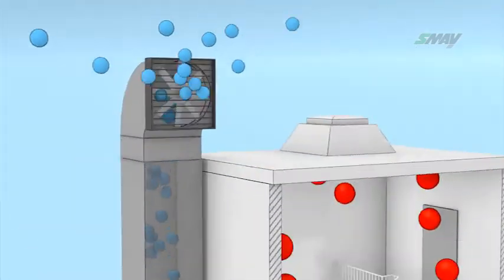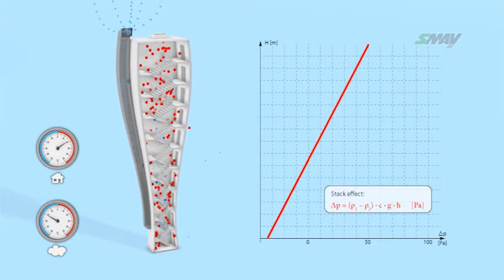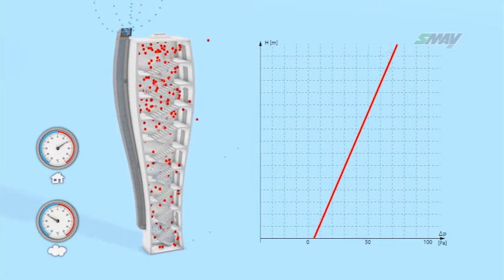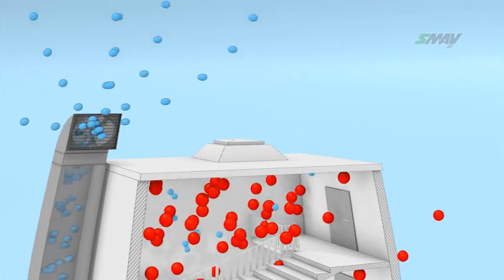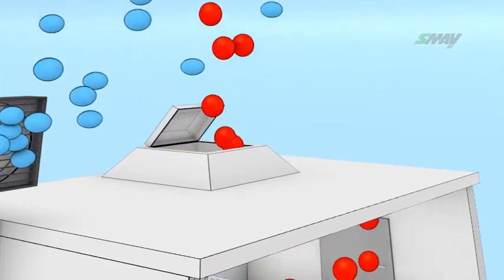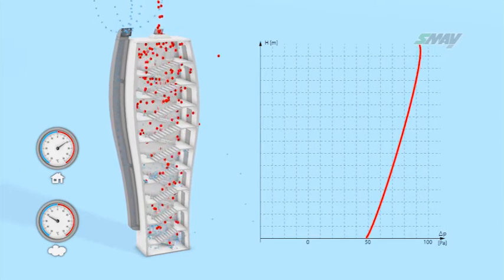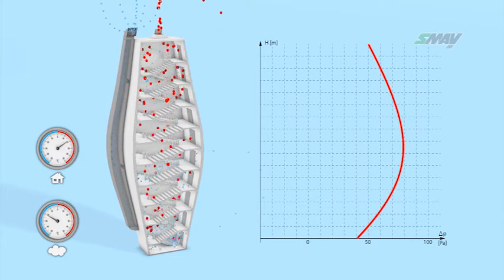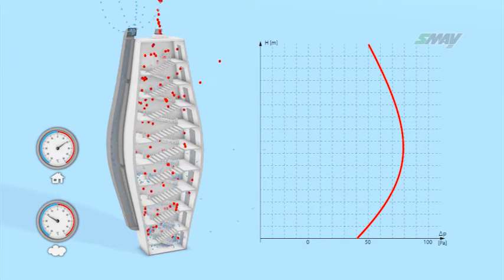However, if air is supplied to the stairwell at a temperature significantly below that of the inside, then pressure stratification will occur as a result of the stack effect. The supply of large amounts of air causes a rapid increase in pressure, but the increase will not be uniform across the entire height of the stairwell — the stack effect will disturb its distribution. A pressure increase in the upper parts causes the barometric overpressure dampers to open, maintaining pressure at no more than 50 pascal. Once the dampers open, pressure in the entire stairwell changes and its value equals the resultant of the flow resistances relative to the size of the air stream and the stack effect.